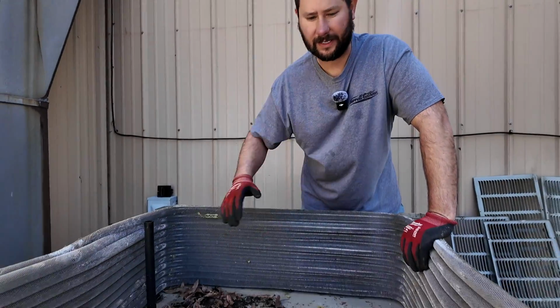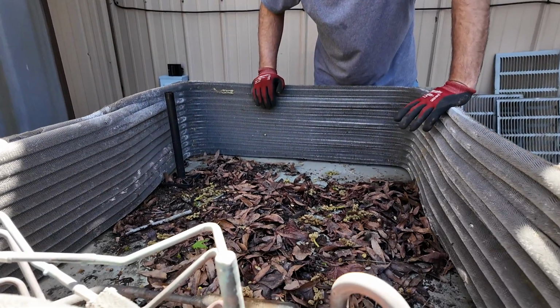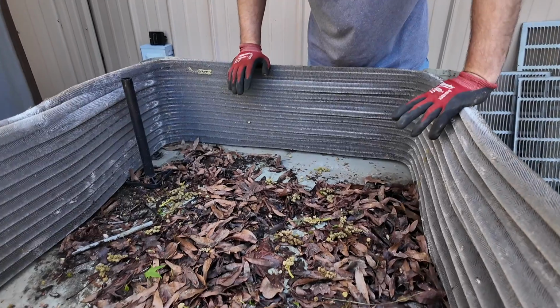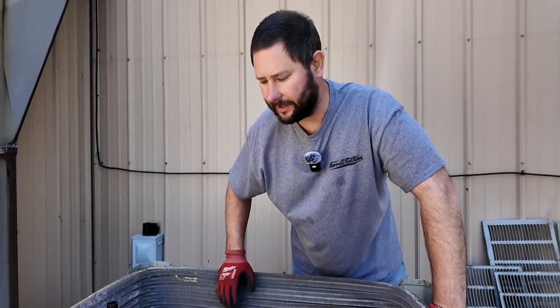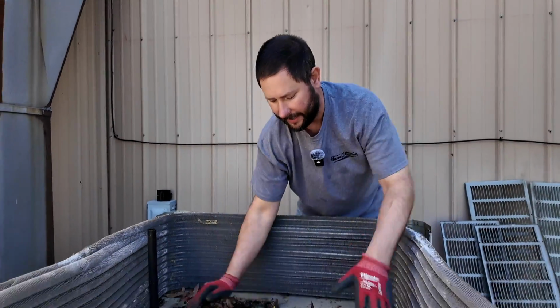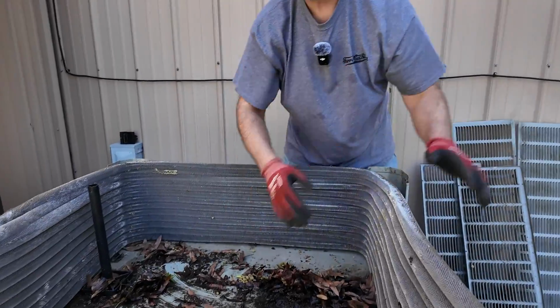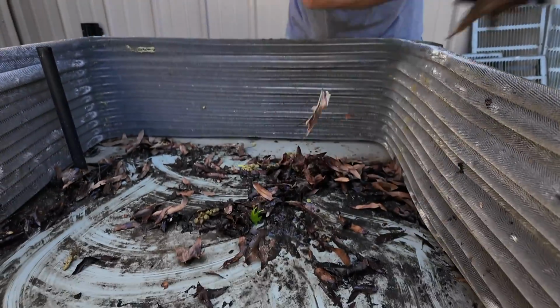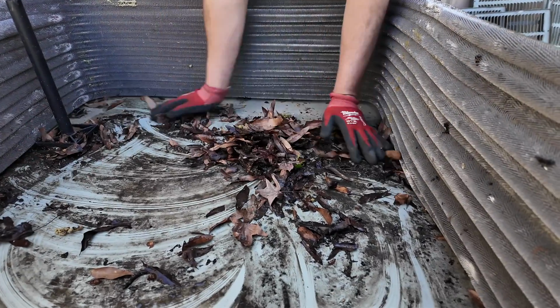As you can see, this unit's very dirty. You can see there's a bunch of leaves inside, and this is why you need annual maintenance. If you've got a vacuum cleaner, definitely use it. If you've got gloves, just scoop all this up and throw it out. We got to do this before we can start using our coil cleaner.